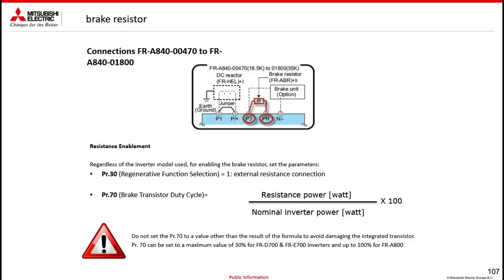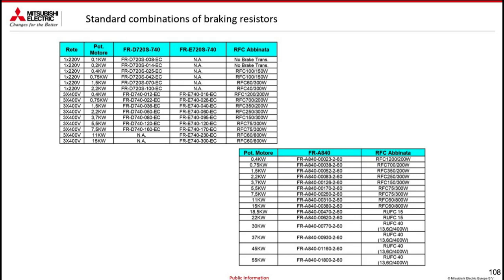For its activation, it is very simple. Parameter 30 at a value of 1, which I call connected to an external braking resistance. Parameter 70 is given by a calculation: the power of the resistance expressed in watts divided by the nominal power of the inverter in watts, in percent. Such a value I am going to set in parameter 70. This is an example of a combination of resistances defined by Mitsubishi Electric.